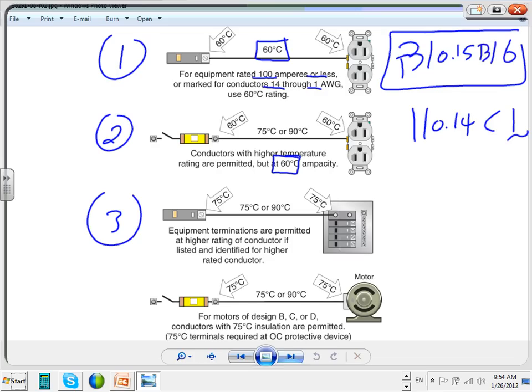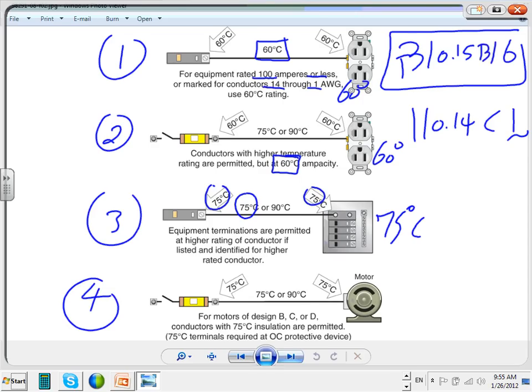Number 3: if the equipment terminals are permitted, so we have a 75. If the terminal is rated for 75 on both sides, and the conductor is rated for 75 or higher, then I can go to the 75-degree column. In this case, this is the 60-degree column. And number 4, for motors, guys: if the lugs of the motor are rated for 75 and the conductors are 75 or higher, for these designs of motors, I can go to 75-degree, no question asked.